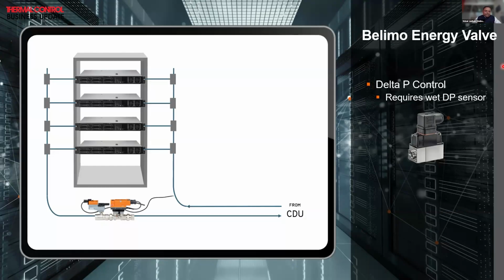And this is one temperature sensor, and another temperature sensor is inbuilt. That's how it calculates the delta T. And then there is a pressure transmitter across supply and return, and that is again connected to the Belimo energy valve, which is the pressure independent valve. This is the equation we all know, and if we convert, GPM is equal to CV into square root of delta P. It's the standard equation.